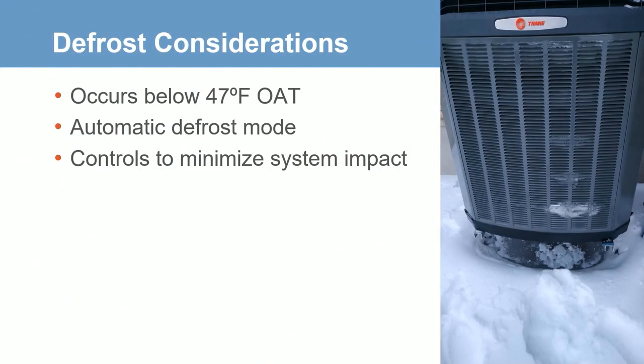Now let's take a look at defrost implications and considerations. Low outdoor air temperatures can cause the outdoor coil temperature to drop below freezing, potentially resulting in frost accumulation on the coil. Defrost typically only occurs below 47 degrees outdoor air temperature. Air-to-water heat pump units will automatically enter defrost operation when it's required. Many air-to-water heat pump unit controls have intelligent defrost control to minimize defrost while maximizing unit heating efficiency and capacity. Most controls also limit defrost to one circuit or module at a time to help minimize the temperature impact on the system.